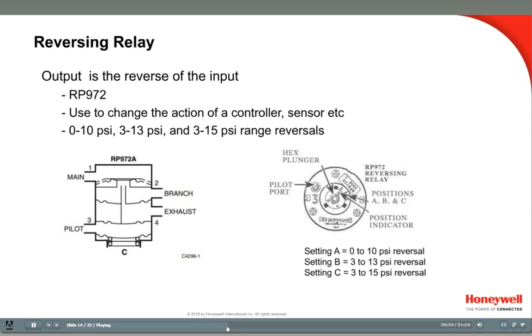There are three pressure settings on the reversing relay. The factory default is position B. In this setting, the RP-972 will reverse a 3-13 signal. This is the most common setting for this relay. Be careful to ensure that the switch is fully clicked into the desired setting for correct operation.